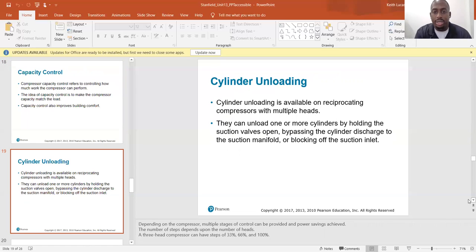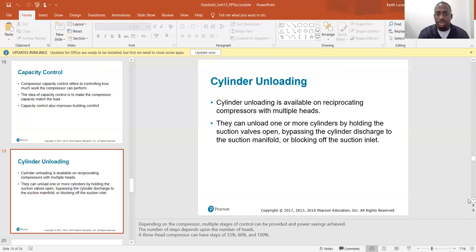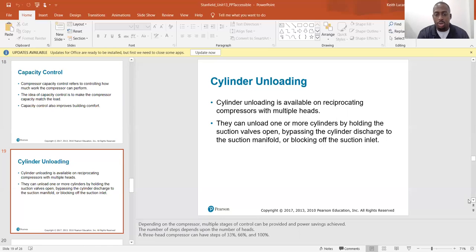Cylinder unloading is available on reciprocating compressors with multiple heads. They can unload one or more cylinders by holding the suction valves open, bypassing cylinder discharge to the suction manifold, or blocking the suction inlet. Multiple stages of control and power saving can be achieved — a three-head compressor can operate at 33 percent, 66 percent, or 100 percent capacity.